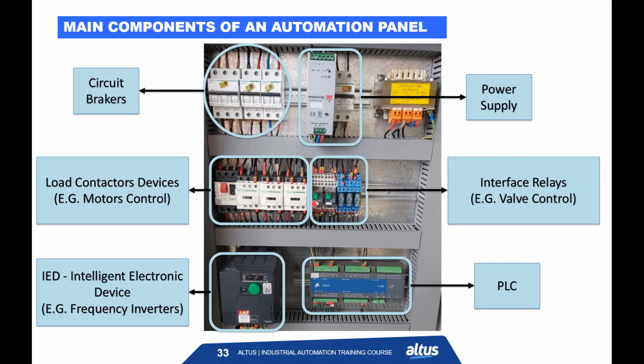Here are some other devices that can be used: interface relays, just to support the load, because of course this compact PLC has limited current to support. So we use this kind of relay. For example, if you have a valve that consumes 5 amps or maybe more, you need to use these interface relays. Here is an example with an IED, intelligent electronic device, for example a frequency inverter, and all of these connected to a PLC.